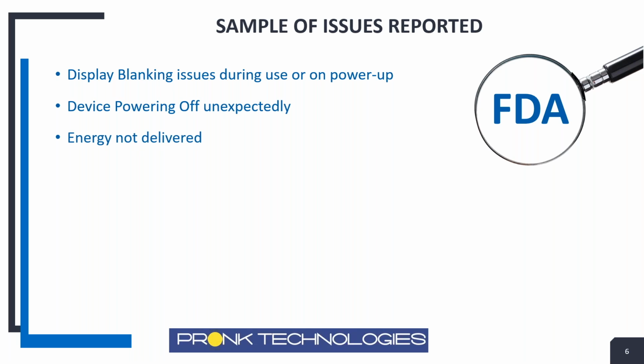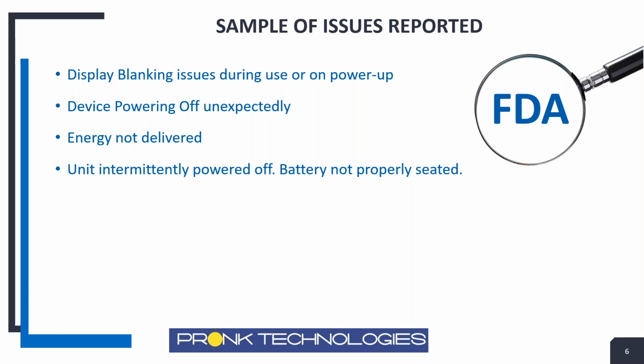Energy not being delivered on the defibrillator. So you're trying to defib the patient, maybe pace the patient, and it's not delivering the energy when it's supposed to. So a number of issues on that. You can see one common thing is that the unit was powering off, even on battery power, trying to use the unit on battery power and it's not working. Lots of incidents reported about battery problems.